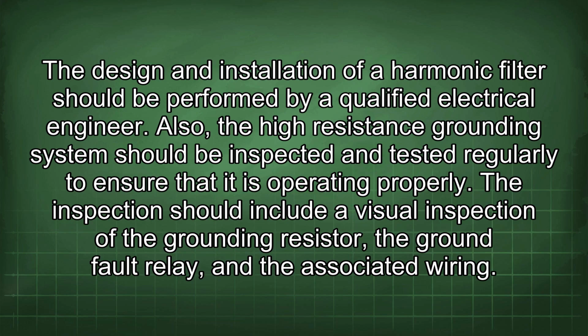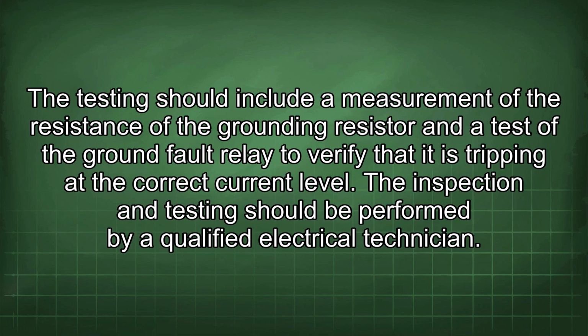Also, the high-resistance grounding system should be inspected and tested regularly to ensure that it is operating properly. The inspection should include a visual inspection of the grounding resistor, the ground fault relay, and the associated wiring. The testing should include a measurement of the resistance of the grounding resistor and a test of the ground fault relay to verify that it is tripping at the correct current level. The inspection and testing should be performed by a qualified electrical technician.